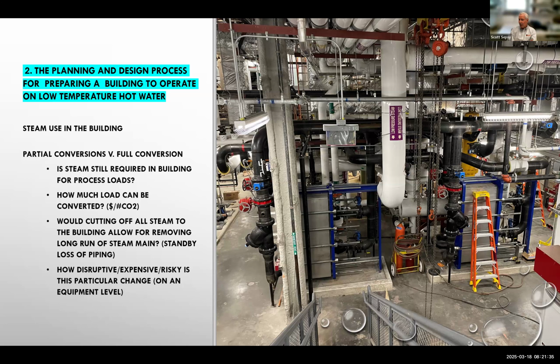However, converting the mechanical equipment, including preheat coils and domestic and lab hot water heaters, reduced the campus steam demand and carbon significantly. And it gave us load for our new heat pumps, which don't have great turndown ability. If you think about the metric of dollars per pound of CO2 eliminated, laboratory preheat coils are the best bang for the buck. The building primary hot water system and service was sized to support the future solutions to the process equipment changes. Those future solutions may include more electrification within the buildings. And so you have to evaluate spare electrical capacity too.